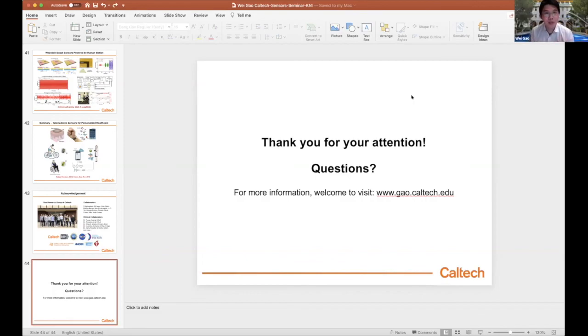Yeah, it's a very good question. Firstly, we are not doing implantable devices, so the sweat composition is much simpler compared to blood. The fouling is not as severe. And again, we are not using an implantable device for several months. We use it for days or weeks. As I said, it's disposable, we can replace it. We just need to make sure that within days or weeks, it can maintain the same level, or a very similar level, within error tolerance, I would say.